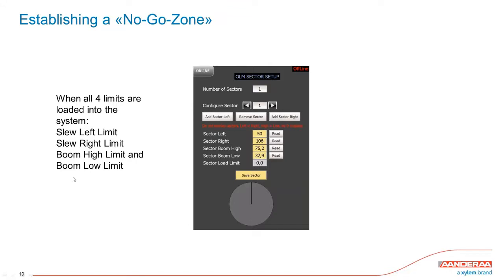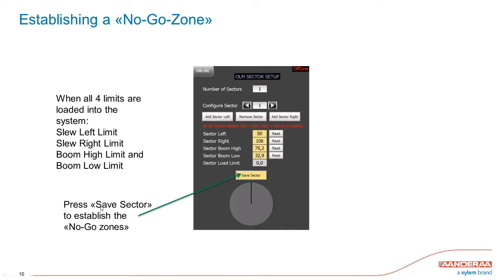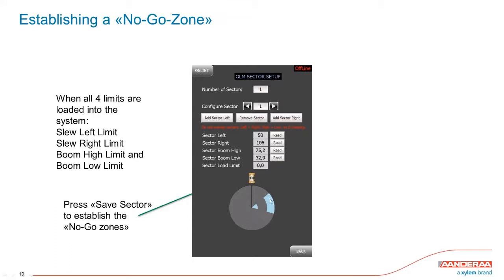One no-go zone is defined by four angles: two slew angles and two boom angles. There is also a fifth parameter — the Sector Load Limit — which means a sector can be valid only when the load exceeds a certain value. For instance, entering four tons means the sector is only active if the hook load exceeds four tons; otherwise it's valid for all operations. When done, press 'Save Sector.' The saved sector is shown on the map in light blue, indicating the no-go area both below and above the defined angles.